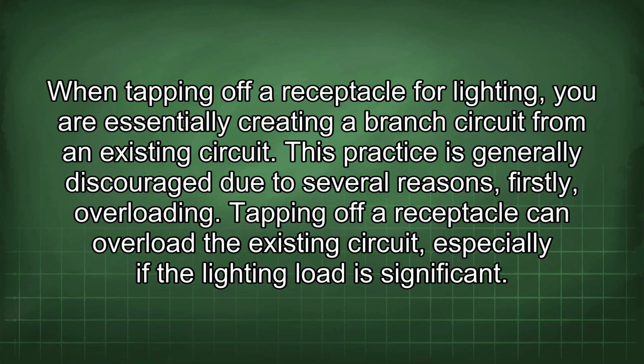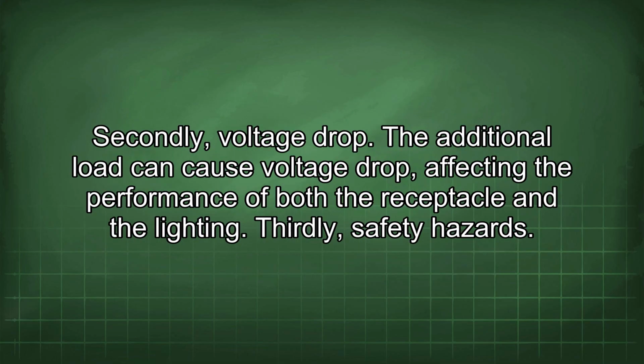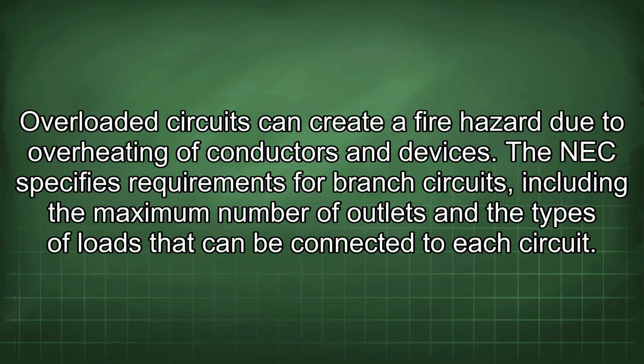Firstly, overloading. Tapping off a receptacle can overload the existing circuit, especially if the lighting load is significant. Secondly, voltage drop. The additional load can cause voltage drop, affecting the performance of both the receptacle and the lighting. Thirdly, safety hazards. Overloaded circuits can create a fire hazard due to overheating of conductors and devices. The NEC specifies requirements for branch circuits, including the maximum number of outlets and the types of loads that can be connected to each circuit.